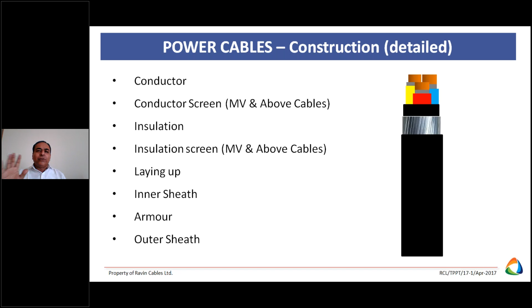materials are selected accordingly: normal cable, flame retardant cables, flame retardant low smoke and halogen. Halogen contents will be less, smoke contents will be less, so that people can safely evacuate from the place. Visibility is there, people can safely evacuate. If halogen contents are more, maybe there's an issue in breathing, people will collapse at the site. So halogen content should be less, so that people can safely or smoothly breathe and evacuate from the place. So it depends on the site. So these are the construction details.